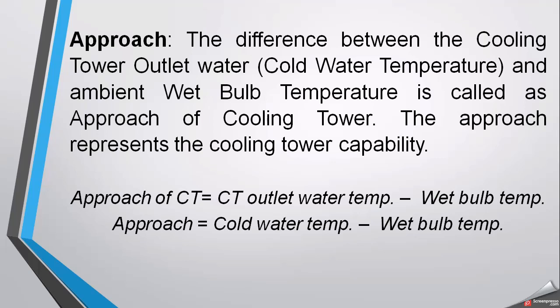The other term used in this calculation is approach. The difference between the cooling tower outlet temperature (cold water temperature) and the ambient wet bulb temperature is called the approach of the cooling tower. The approach represents the cooling tower's capability — how much it can reduce the temperature of the hot water coming from the system. Approach equals cold water temperature minus wet bulb temperature.